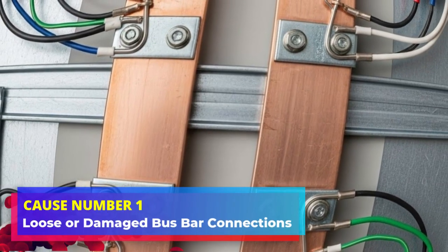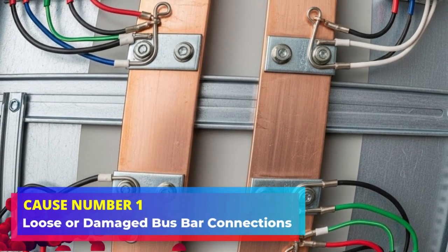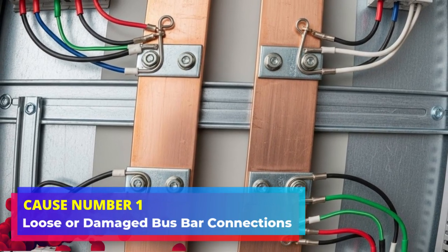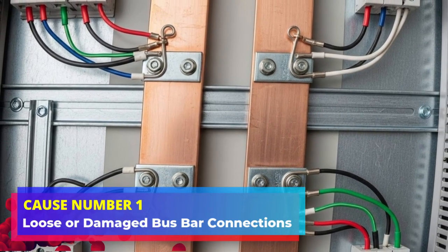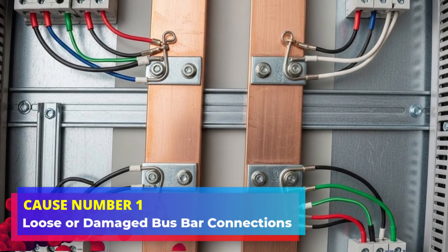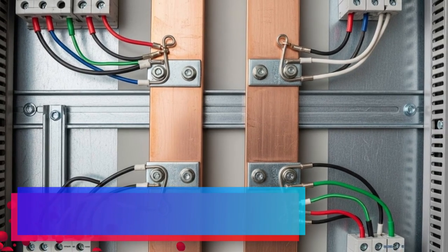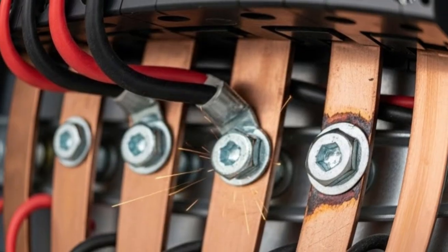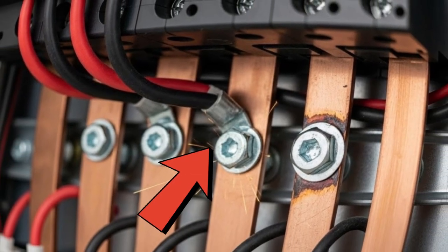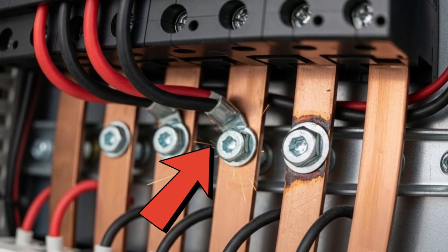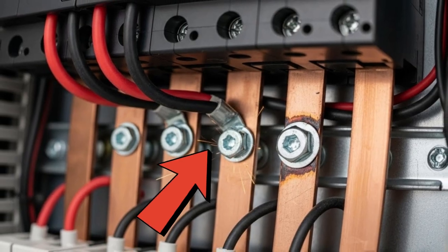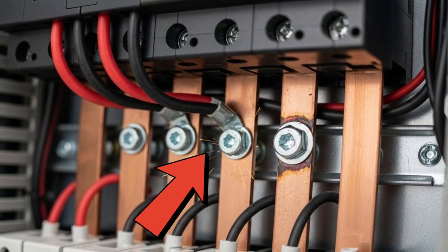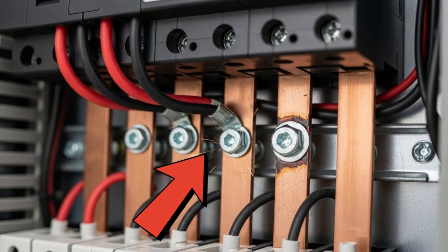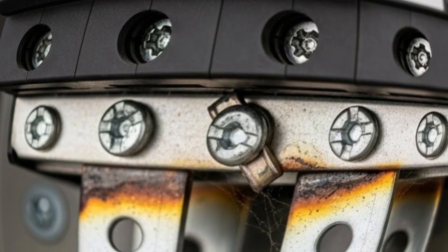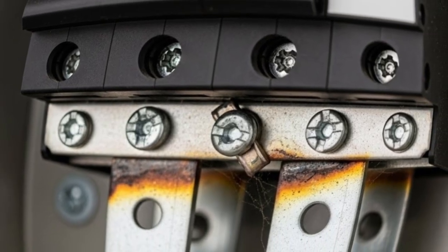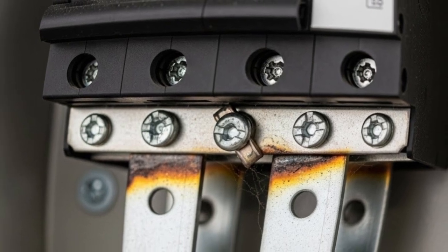Inside your electrical panel, 2 metal bars called bus bars run vertically down the center. These bus bars receive power directly from your main breaker and distribute it to every individual circuit breaker in your panel. Over time, the connection between your main breaker and the bus bars can loosen. This happens from thermal expansion and contraction. Every time your panel heats up under load and cools down again, metal components expand and contract slightly. After years of this cycling, connections that were once tight can work themselves loose.